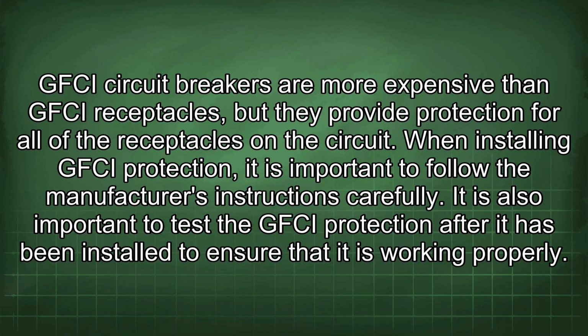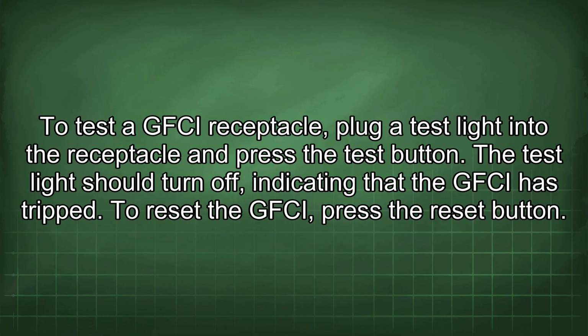It is also important to test the GFCI protection after it has been installed to ensure that it is working properly. To test a GFCI receptacle, plug a test light into the receptacle and press the test button. The test light should turn off, indicating that the GFCI has tripped. To reset the GFCI, press the reset button.